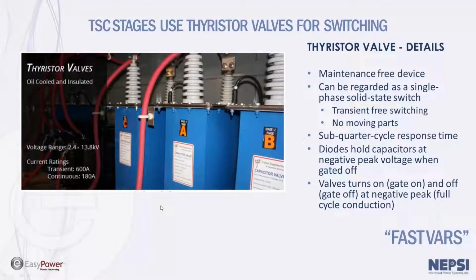The capacitor assist motor starter, or the actiVAR as we call it, utilizes thyristor valves, and the picture here shows 3 thyristor valves. They're single phase devices. They're filled with oil, so they're cooled and insulated with oil. It's a maintenance free device. It can be regarded as a single phase solid state switch. Operates much the same way as a vacuum switch might operate, or a circuit breaker. Send a signal to turn on, send a signal to turn off.